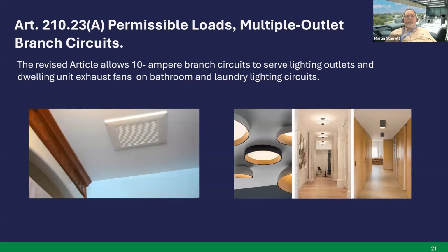And part of this whole 10 amp conversation is in 210.23(A), permissible loads, multiple outlet branch circuits. The revised article allows 10 amp branch circuits to serve lighting outlets and dwelling unit exhaust fans on bathroom and laundry lighting circuits. So pretty much that 10 amp branch circuit will only be able to be used for these items, no receptacle outlets. You'll be able to use it for lights and exhaust fans that are on lighting circuits.